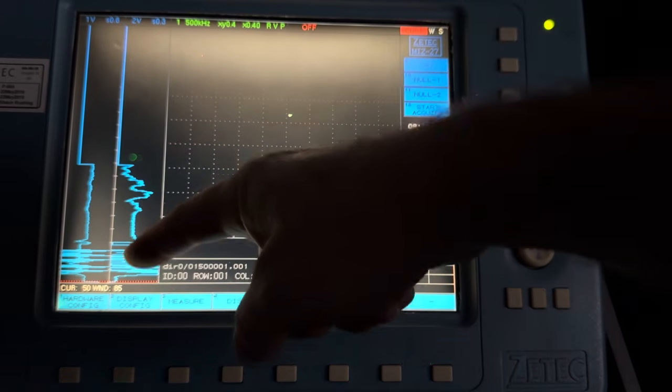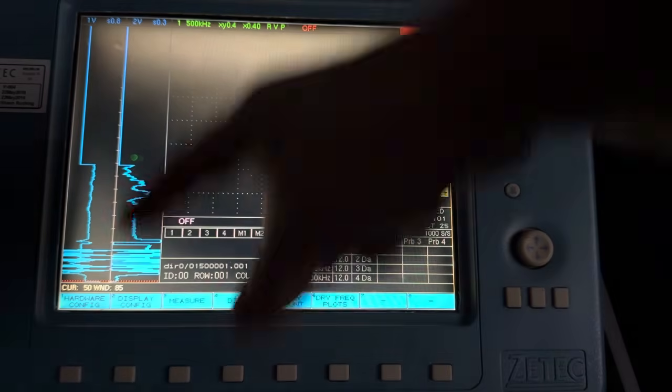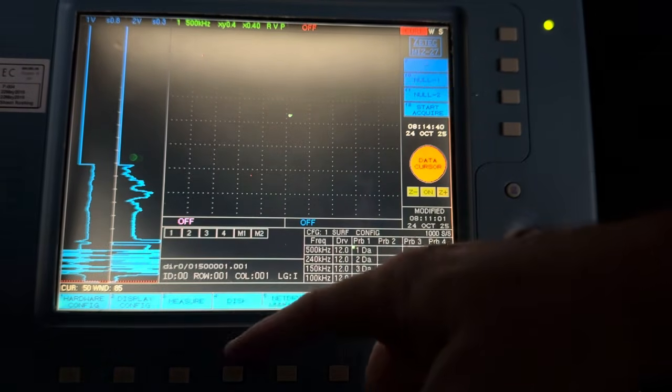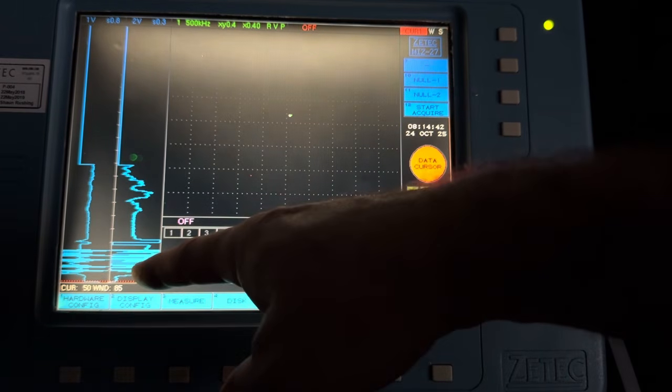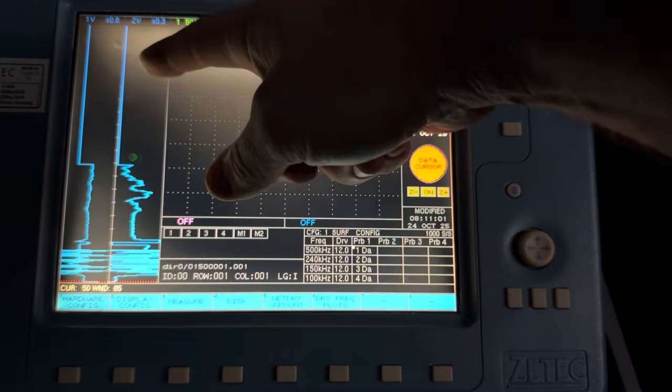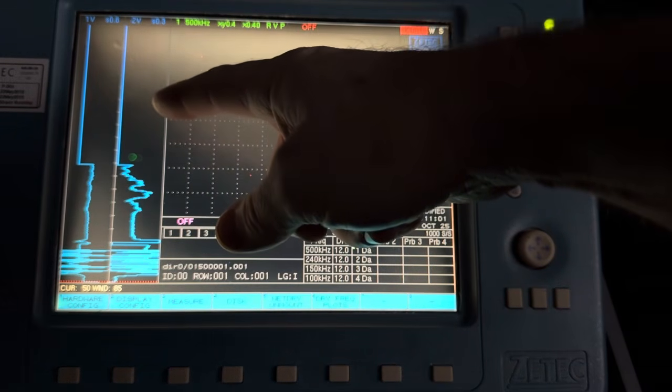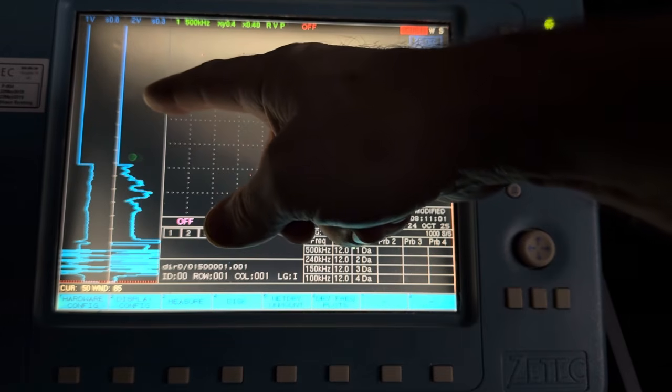And when you get to the bottom of the strip chart and I hit stop, you're going to have some data displayed. The thing that the probe saw first when I started recording is going to be at the bottom of the strip chart, so that's the earliest in time data. And the thing up towards the top of the strip chart is going to be the last thing that the probe saw before I turned off the tester or turned off the recording mode.